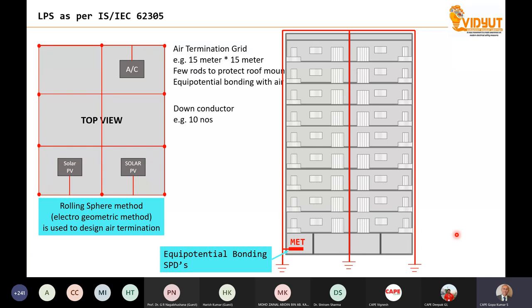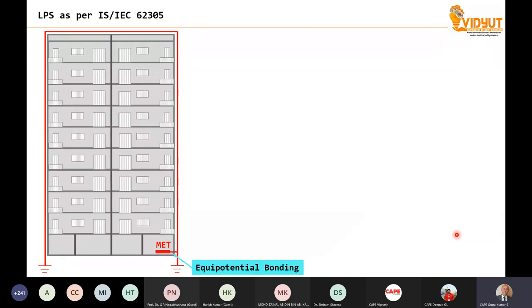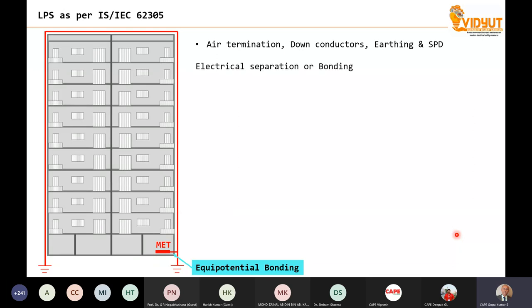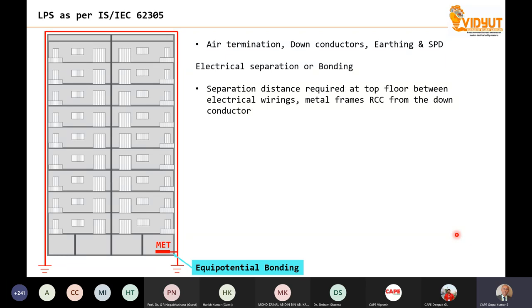The calculations are given in the standard on how to design the earth electrode and so on. And in modern buildings, the easiest way is to make a foundation earthing. That means the structural steel, the steel reinforcement inside the building, can be used as the earth electrode. So this is how the lightning protection system is designed according to the IEC 62305. Now, another important subject of this particular design is called electrical separation.